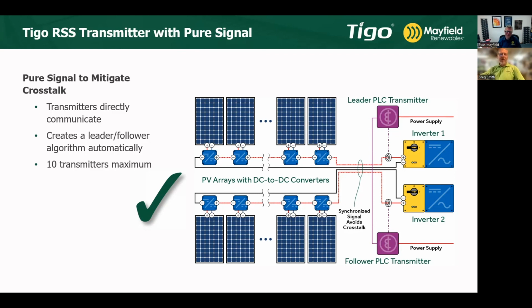So what we did was essentially give a massive upgrade to our RSS transmitter and give it the ability to sync to other transmitters. And what we've essentially done is eliminated this crosstalk issue, because all the transmitters now, regardless of how many inverters you have, how many CTs or transmitters, the signals are all synced together, so they're not at different times, different amplitudes, different whatevers. They're all the same. So it doesn't matter if you put them in the same conduit or overlap them in the same cable tray. We just don't have this crosstalk issue anymore.